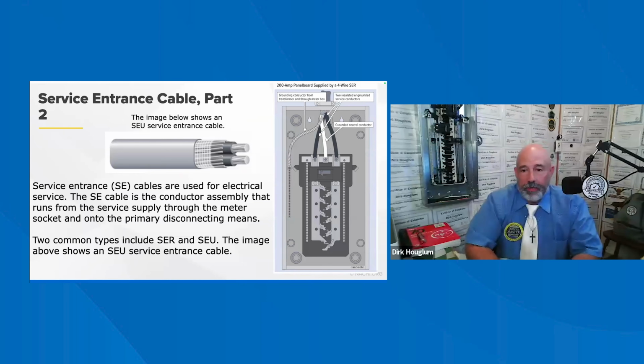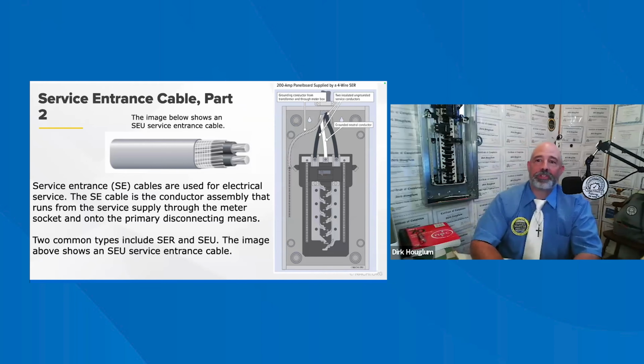I feel like we've seen this slide before, right? The SEU cable is a 3-wire service cable and has 2 hot wires and 1 neutral. The neutral is usually stranded and wrapped around the cable, giving it an oval shape. The SEU cables don't have a grounding wire, which means that they can only be used up to the main service disconnect, not beyond it, because after that point, neutral and ground must be separated for safety.